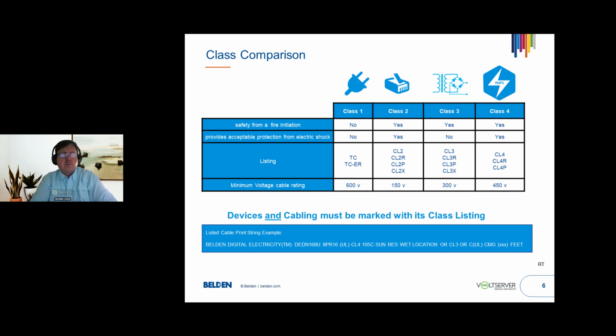So the listings for those cables are as shown. The CL2 is the general purpose, the R indicates riser, P plenum, and X is limited use. We have those same certifications except for limited use for Class 4. So these Class 4 circuits, which are really cables in our lingo, can be utilized in the same pathways and spaces as Class 2 cables.